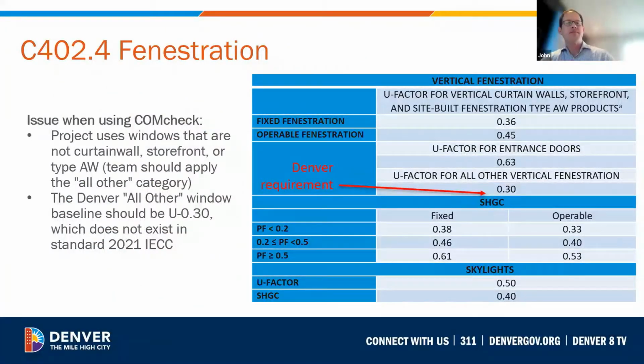Now for fenestration, there's an update to add a new U factor requirement, as I briefly mentioned before, for all other fenestration. This covers architectural windows and other assemblies not covered under the other categories. For this type of window, a maximum allowed U factor is 0.30, which is slightly more stringent than the other assemblies. Now note that since this is a Denver-specific update, the ComCheck will need to be updated to reflect the new prescriptive requirements and new C406 energy credits of the Denver Energy Code.